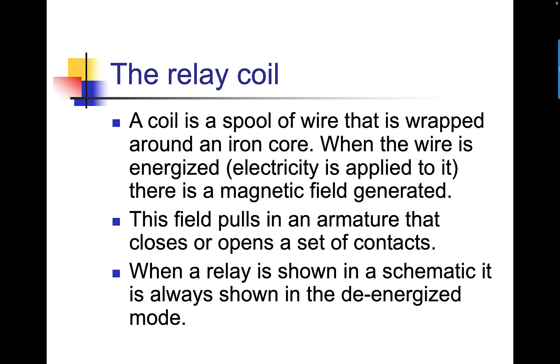This field pulls in an armature that opens or closes a set of contacts. When a relay is shown on a schematic, it is always shown in the de-energized mode or position. When we write schematics, especially ladder diagrams, we show everything de-energized.